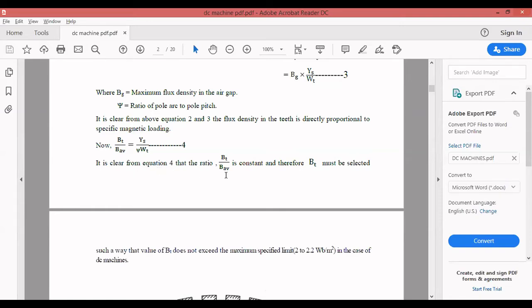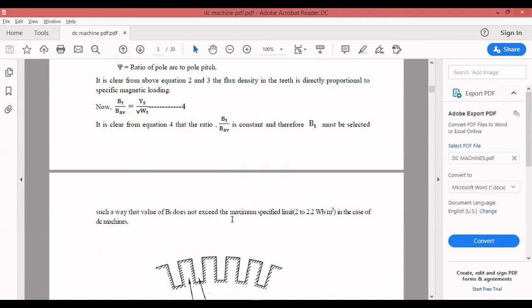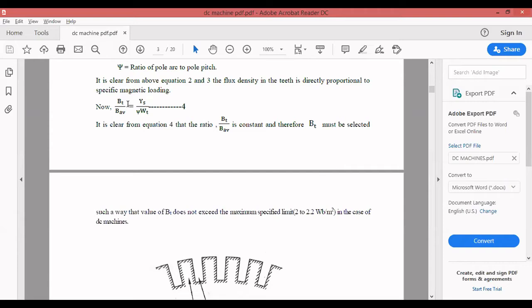If we take a parallel slot, the tooth will be tapered, meaning the flux density will not be uniform from the bottom to the height of the tooth. Tooth flux density will vary from minimum to maximum over the tooth height, because the width is narrower at one end and wider at the other. Thus, a low value of specific magnetic loading is selected for small machines to compensate for the flux variation.